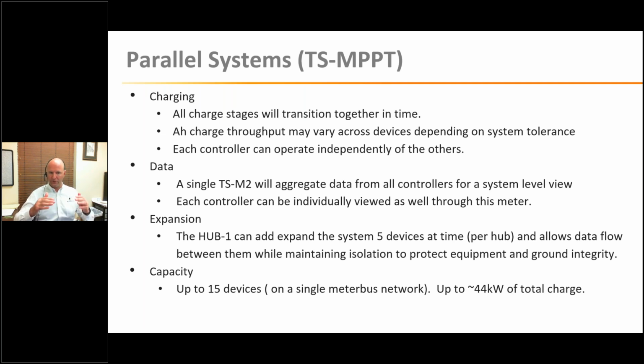So they'll go through your bulk, your absorption stage when it reaches full, and then all gradually transition to float. They won't always do it at the same time, but that's fine because the battery doesn't always need all the current of all controllers. You'll have several of them slowly transition into those stages over time, and that's usually fine because you're limiting current anyway at that point in absorption or float.